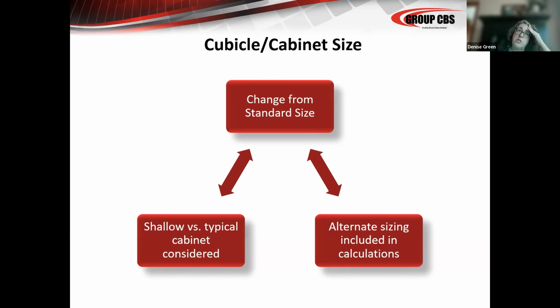Now, I will tell you, in both the 2018 and the 2021 NFPA 70E, they have not made it a requirement for labels to be recalculated. So the standard says that your arc flash labels and your study must be reviewed every 5 years. It must be documented that it's reviewed, and any significant changes that were made to the system, those labels must be recalculated. But they have not come forward and said, hey, we made this change in 2018 to the calculations, everybody that had their stuff done before that, you have to redo your labels. That has not happened yet. But it's important for you and your staff to know that the number on the label could be different based on the size of the cabinet. Okay, so that's kind of the deal there.